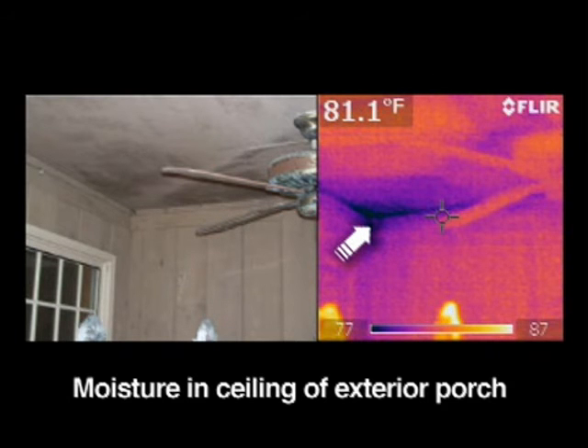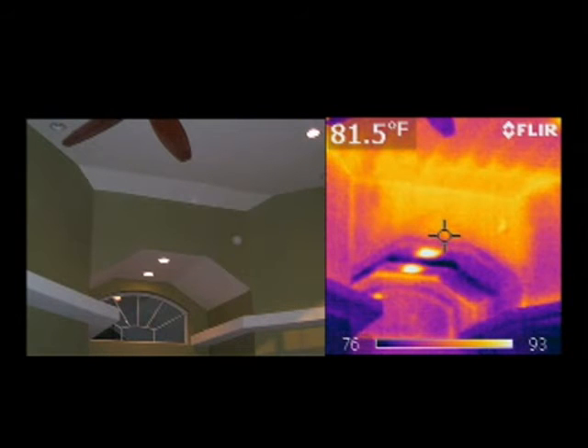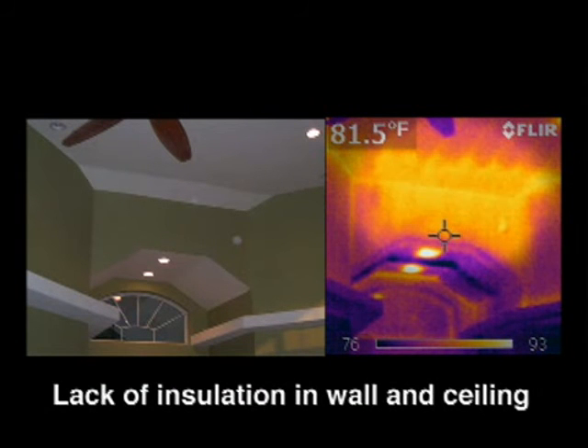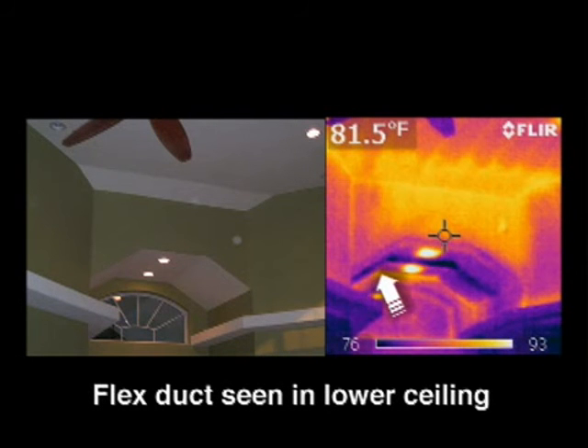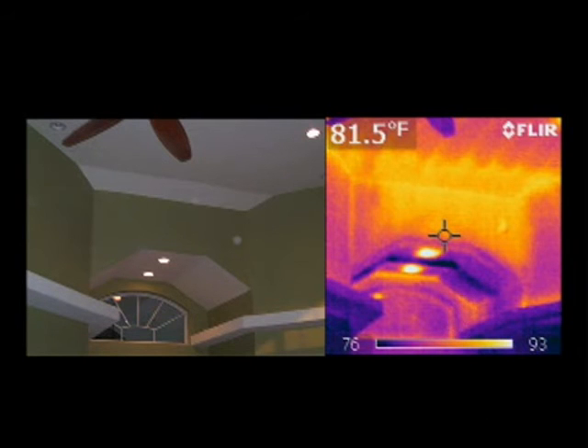The next set of photographs shows a multi-layered ceiling with a lack of insulation. You can see the ductwork traveling across the lower ceiling area. This shows how sensitive the camera is: it picks up the ductwork in the attic, the lack of insulation, the coolness of the lower walls, the different temperatures of the upper walls and ceilings, and clearly shows areas lacking or missing insulation.